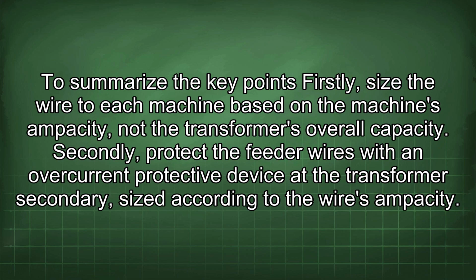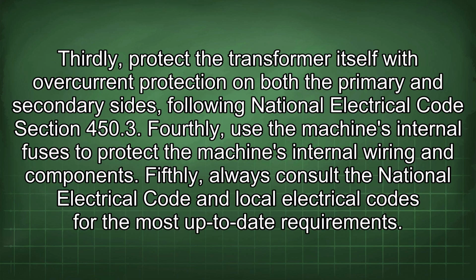To summarize the key points, firstly, size the wire to each machine based on the machine's ampacity, not the transformer's overall capacity. Secondly, protect the feeder wires with an overcurrent protective device at the transformer secondary, sized according to the wire's ampacity. Thirdly, protect the transformer itself with overcurrent protection on both the primary and secondary sides following National Electrical Code Section 450.3. Fourthly, use the machine's internal fuses to protect the machine's internal wiring and components.